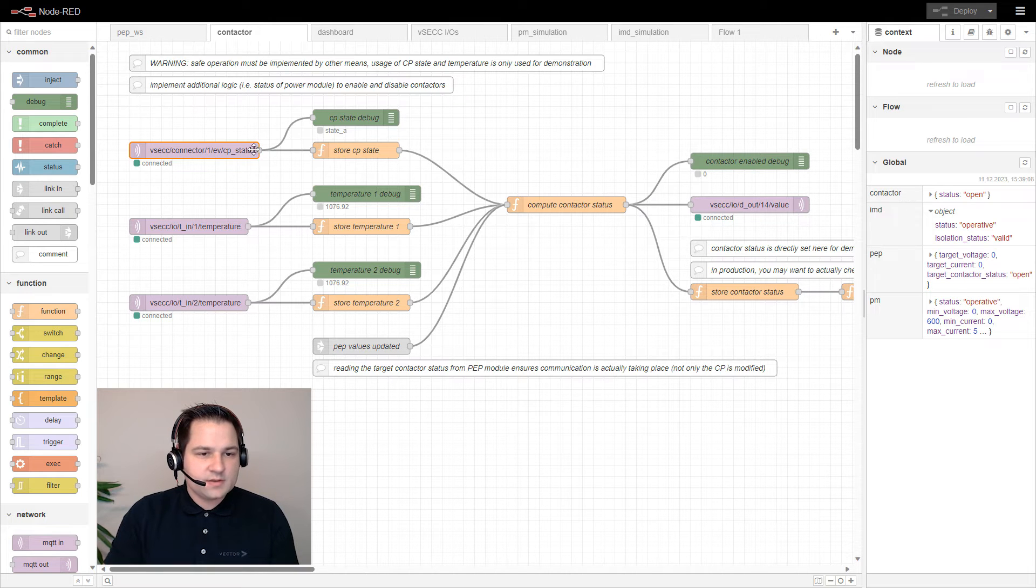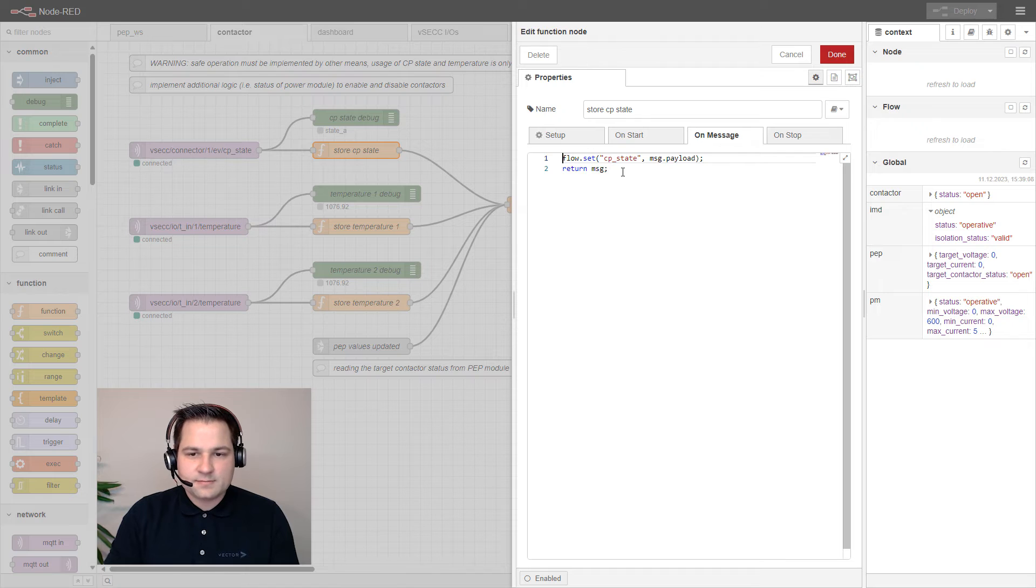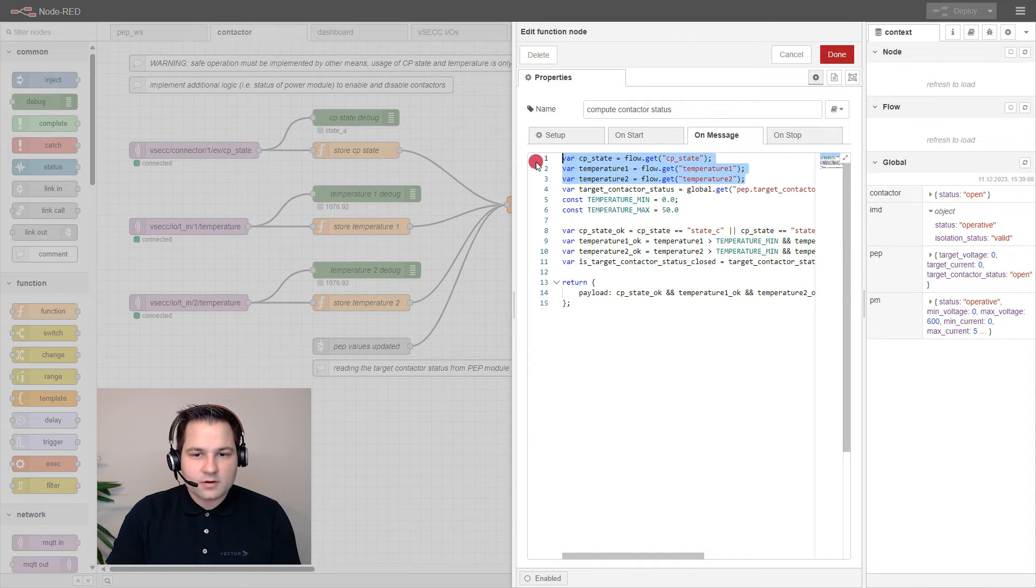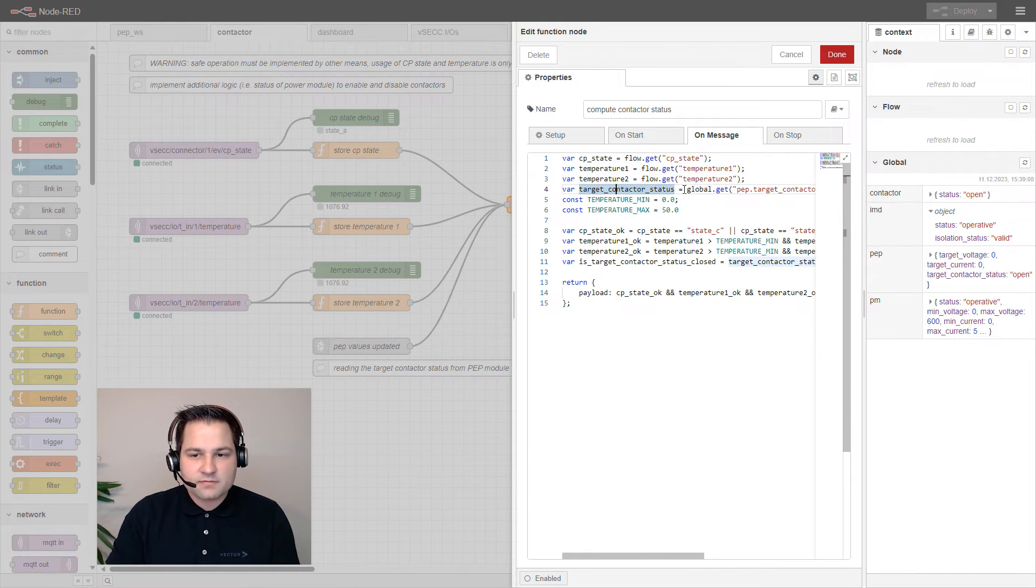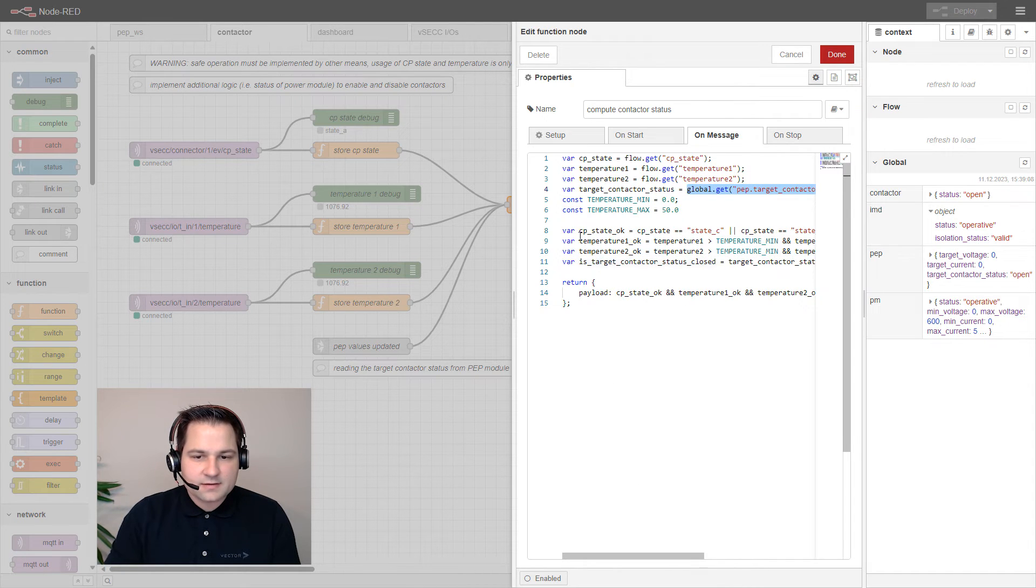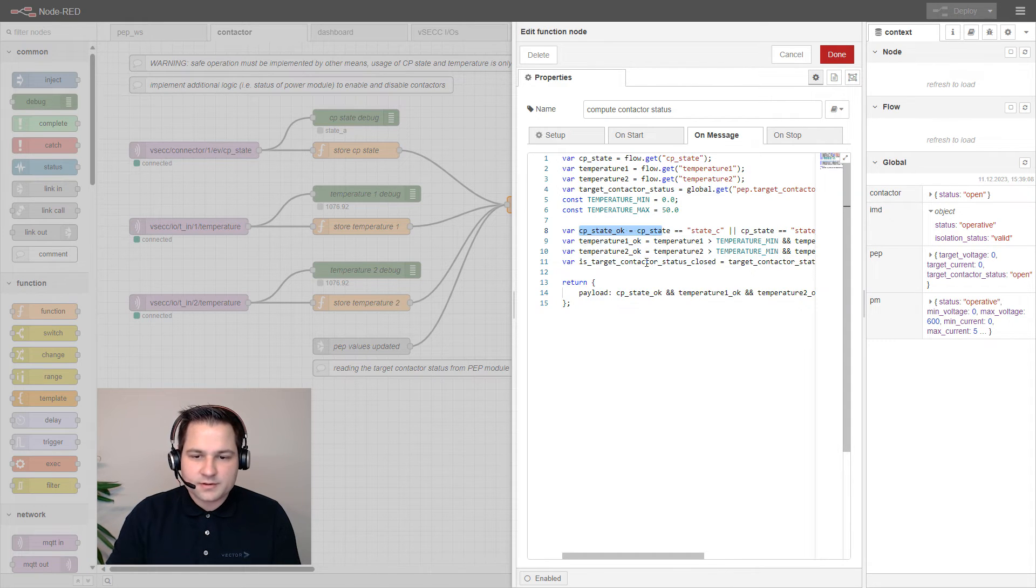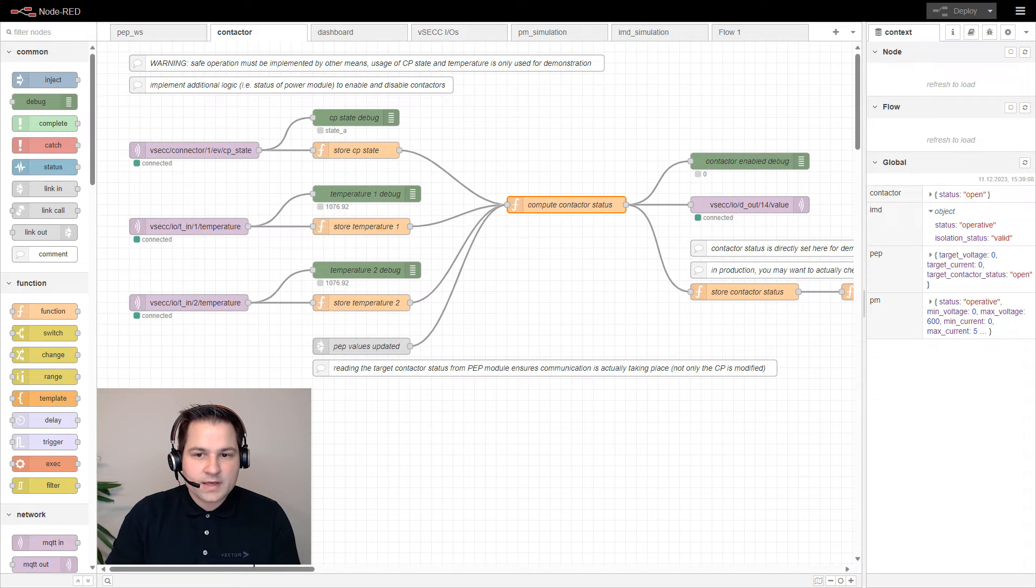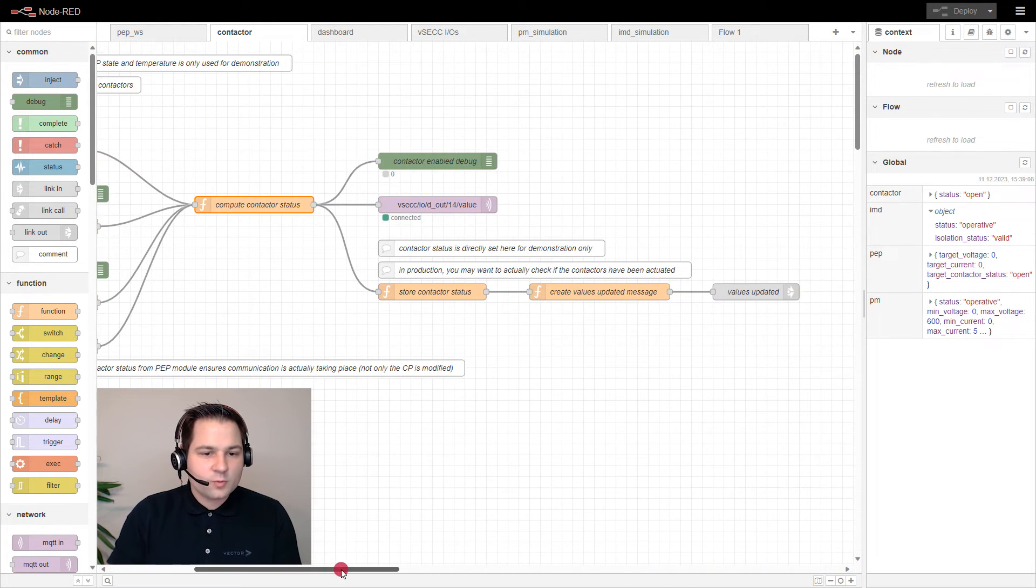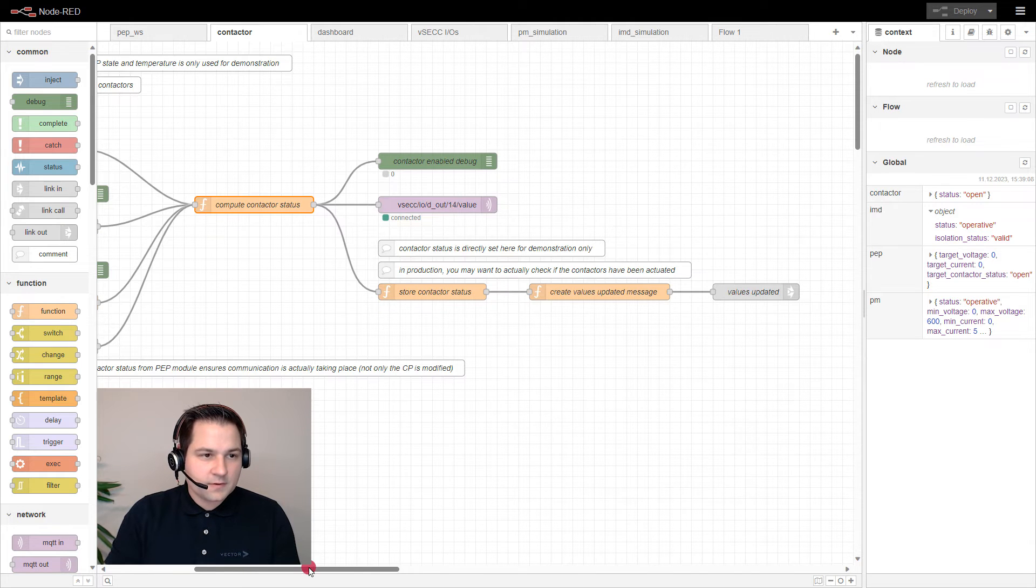As soon as we get the CP state, we first of all store it in our flow space. That's because we want to get all current information if we compute our contactor status. Here we have a JavaScript that first gets all information that we need: the CP state, the temperatures, and the target contactor status. That's getting from the global space. Then after checking if the CP state is correct (so C or D) and the temperature is in range and the target contactor status is correct, we set our payload to true or false. With this information getting forwarded first of all to the debugger and to the output 14, which is connected to the safety relay. Also we store our contactor status in the global space and create a 'values updated' message for the other flows.